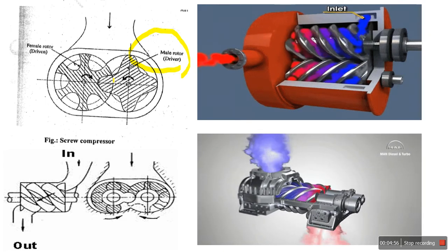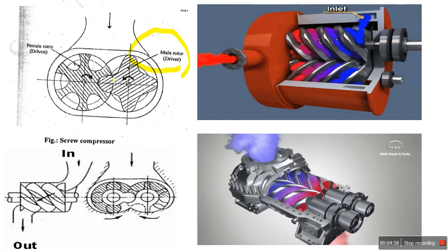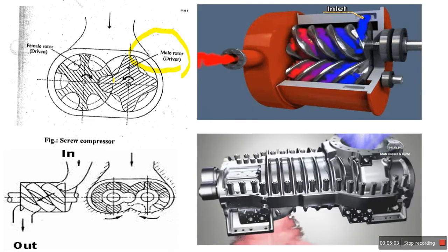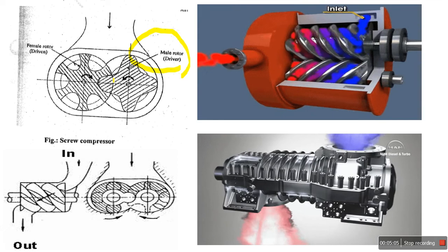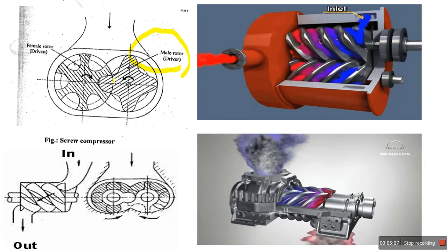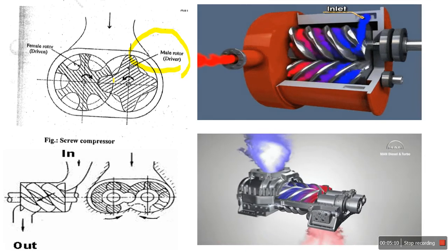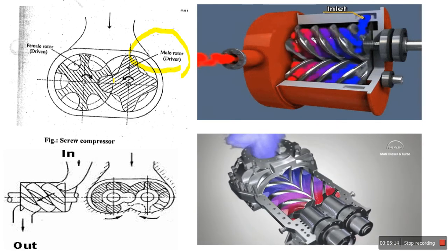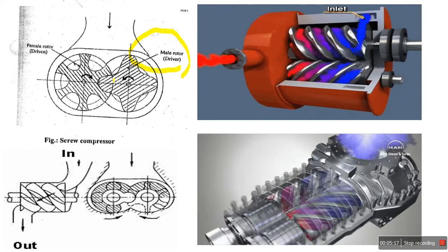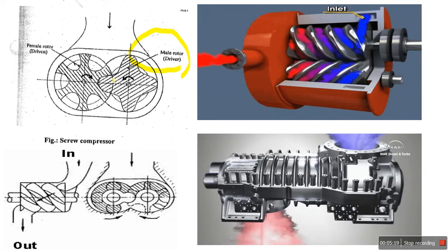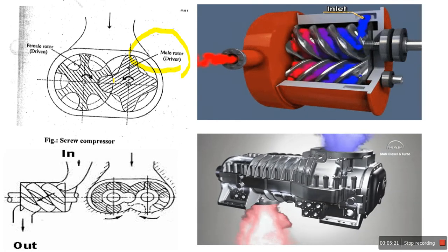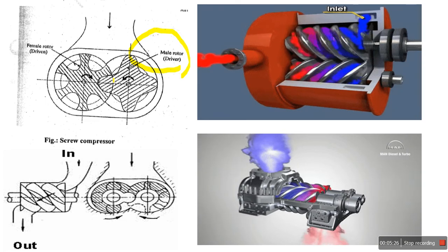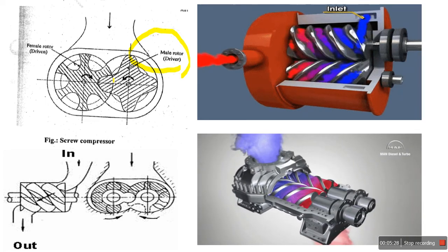The female or driven rotor has six flutes. Regarding the working of the screw compressor — first, during suction: as the rotors begin to unmesh, a void is created on both the male side and the female side, and air is drawn in through the inlet port. As the rotors continue to turn, the interlobe space increases in size and air flows continuously into the compressor.